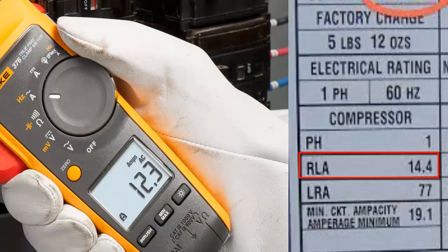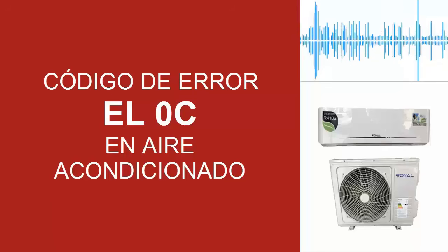Compare the clamp meter reading with the RLA of the equipment. A gas leak causes a decrease in the current consumption. This check is straightforward, and can be done without directly intervening in the air conditioner. Simply use a cable from the equipment's power supply.